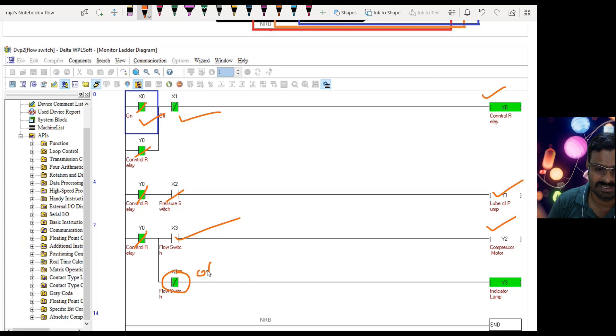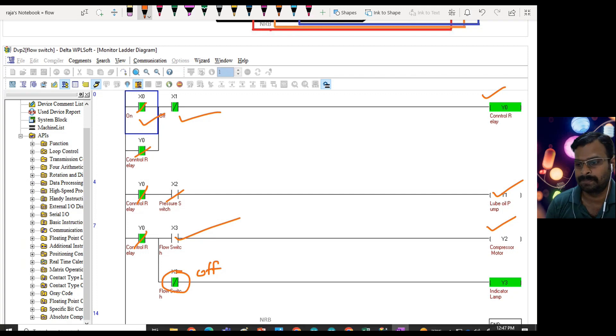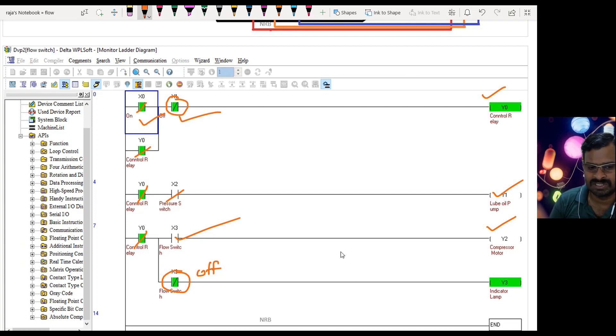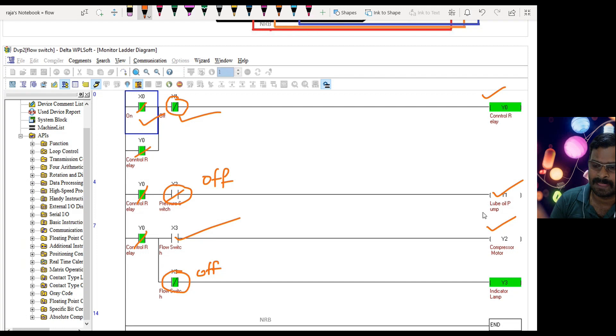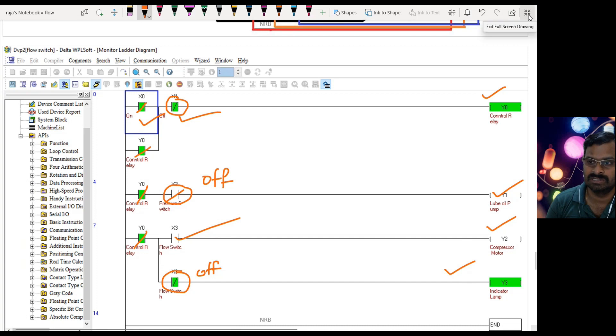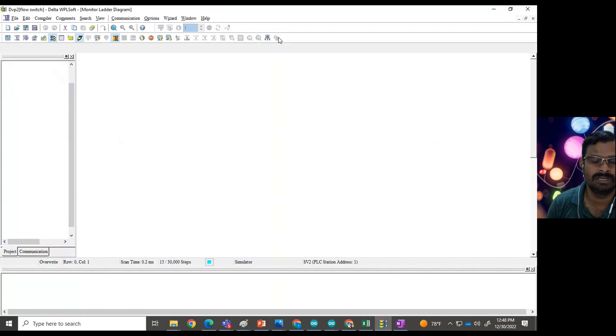When the flow switch detects flow, the compressor motor turns on. When the compressor motor is on, the indicator goes off. This is the sequence followed in the program. To turn off the total operation, switch off the on switch so power flow stops in all rungs. Alternatively, when pressure reaches the set pressure the switch opens, there is no flow from the lube oil pump, the flow switch detects no flow, the compressor goes off, and the indicator comes back on.